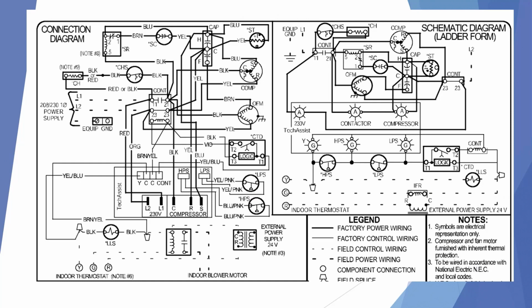It is very important for a service technician to be able to read a wiring diagram. This is a standard wiring diagram with the schematic or the ladder form on the right hand side, which, as we just saw, shows the loads on the line that they are together with. You also have the connection wiring diagram, which shows wire for wire where each wire is landed on each component.